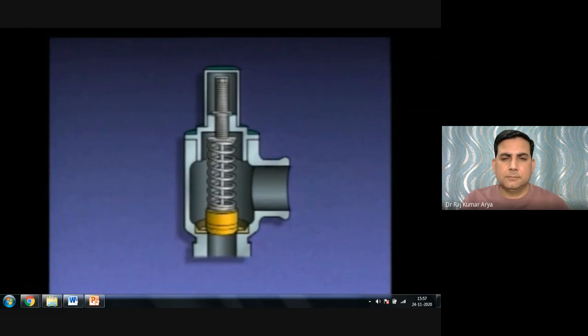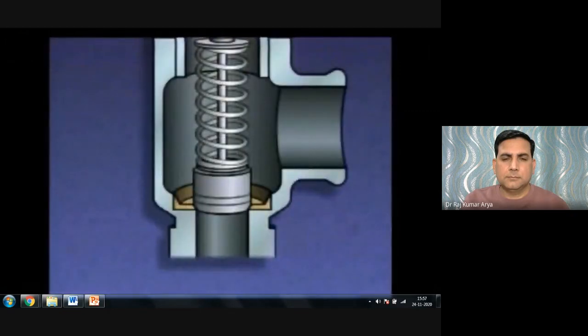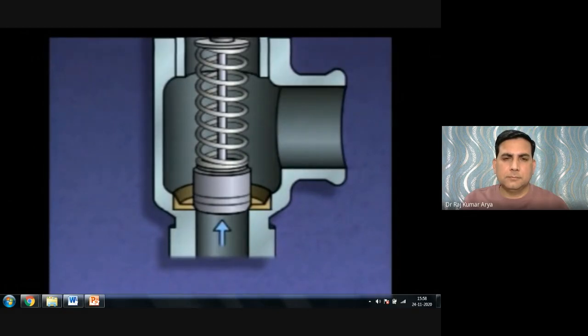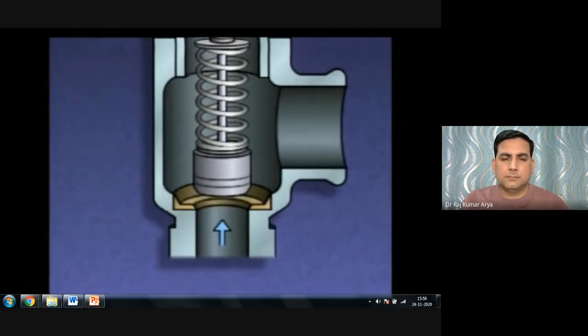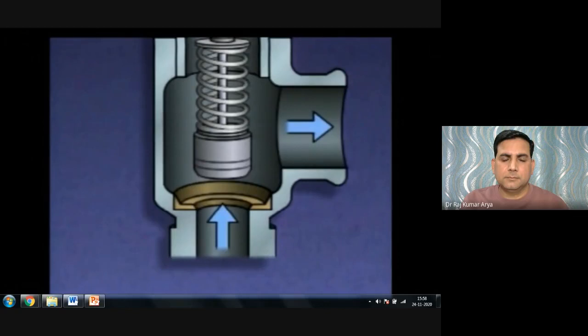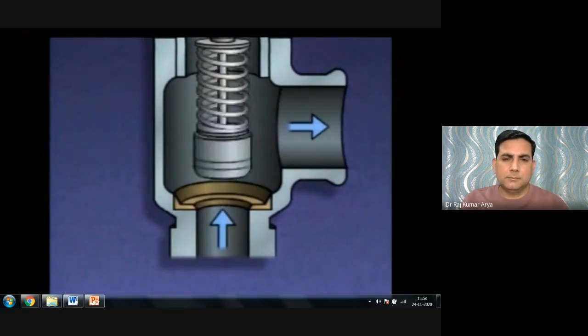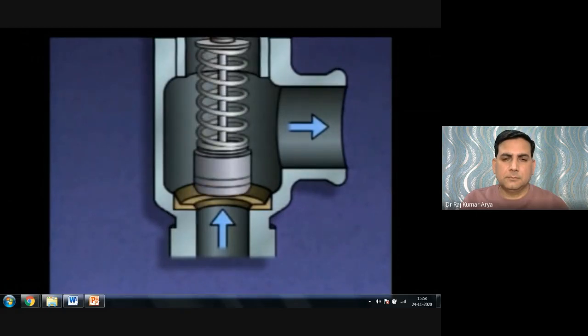The valve body provides a path for fluid flow and holds all other parts in position. The disc rests on the seat, held in place by the spring. A relief valve is set to open when system pressure reaches a predetermined value, say 200 psi. When pressure reaches that value, the pressure on the disc begins to overcome the spring force and the disc lifts off the seat, releasing pressurized fluid through the outlet. As system pressure decreases to just below 200 psi, the spring pushes the disc back onto the seat.